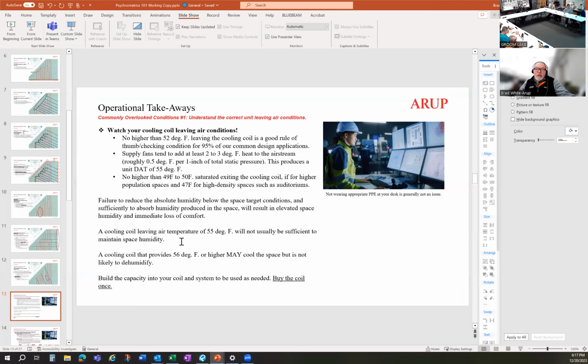And you'll also find that your typical fan is going to, especially if you do a draw-through system where the cooling coil's first, then you follow with a fan, that fan is going to add a few degrees of heat. We all talk about fan heat. We can quantify it a little more easily, but you're typically going to get between 1 and 3 degrees of heat off of your fan. It's not just motor heat, it's the heat of compression, just like a diesel engine piston compresses and raises the temperature, so too do fans when they compress the air into a duct.